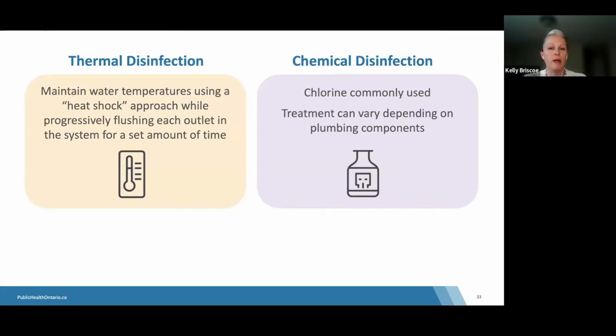So for example, depending on the system, a consultant may recommend increasing the level of chlorine to, say, 4 parts per million over multiple hours, or as high as 50 parts per million for 1 hour. In a healthcare setting, it may be more practical to apply these lower concentrations over a longer period of time, considering the risk of potentially harmful impacts on residents and staff. However, this is always a very individualized approach, and again, why a water consultant can be so beneficial.